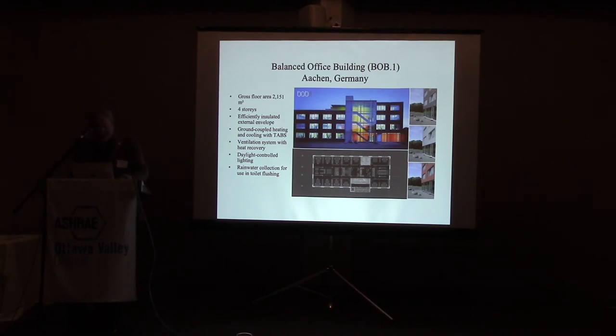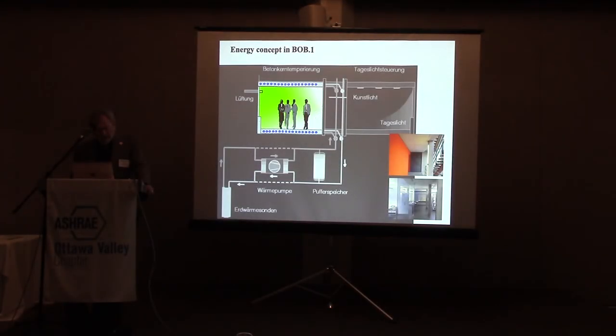So, in this building here, when we look at the system, they had a TABS system and they had a ground source heat pump. But what was done was, for the heating, they used the ground source heat pump, but for the cooling, the heat pump was bypassed, because the ground temperature was low enough to produce a temperature of 16-17 degrees for the cooling.